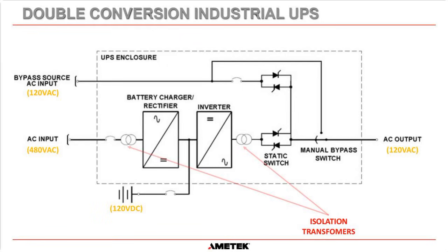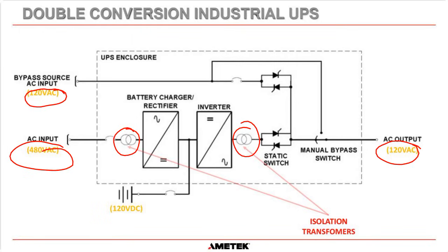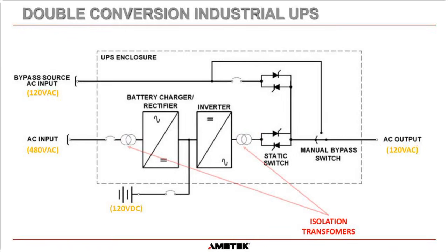And you can see here, usually our output, very similar to the commercial UPS, we use 480 volt three phase on the AC input. But what differs from us and the commercial UPS is we tend to use 120 volts AC output and bypass supply. And we'll explain that in a few slides along. And you can see here, we do have the isolation transformers to prevent faults propagating either onto the loads or back onto the MCC. And our batteries are usually 60-cell lead acid batteries at 120 volts, but we do have some customers who want 240 volt DC batteries. It just depends on the UPS that's being replaced and the backup time that you require. But most systems that we design do have 120 volt nominal battery.